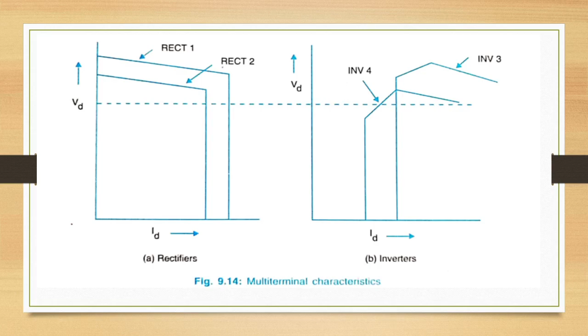HVDC simulator study of a 4-terminal MTDC system indicated the possibility of adverse interaction between the control and DC network dynamics. This can result in multiple mode shifts in rectifiers following a remote 3-phase fault at a rectifier. Commutation failure at the small inverter results in the total DC current diverted into the faulted inverter due to voltage drop in the inverter caused by commutation failure.